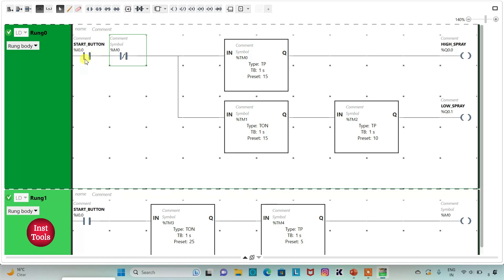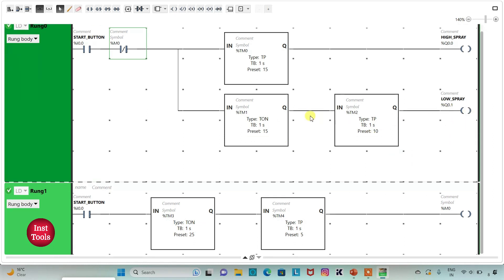When the start button is turned on, high spray will be active for 15 seconds. For low spray there will be a delay of 15 seconds, and after those 15 seconds — during which high spray was active — low spray will run for 10 seconds. After both high spray and low spray, that is 25 seconds total, it will be off for 5 seconds. After those 5 seconds the cycle repeats: high spray for 15 seconds, low spray for 10 seconds, and off for 5 seconds.